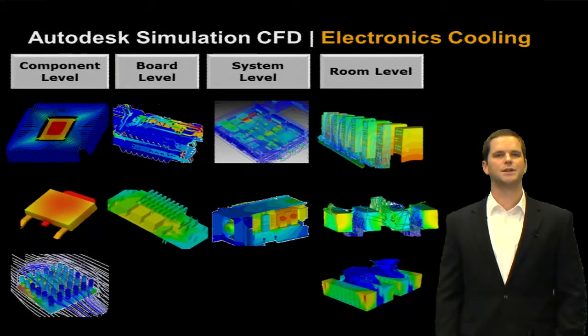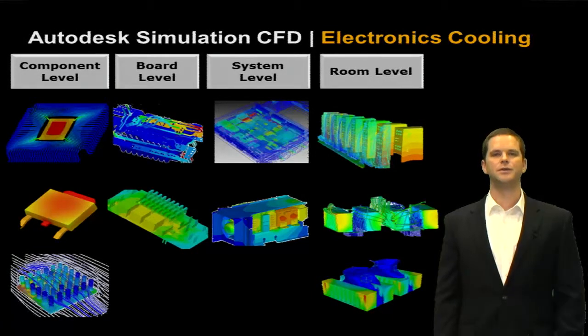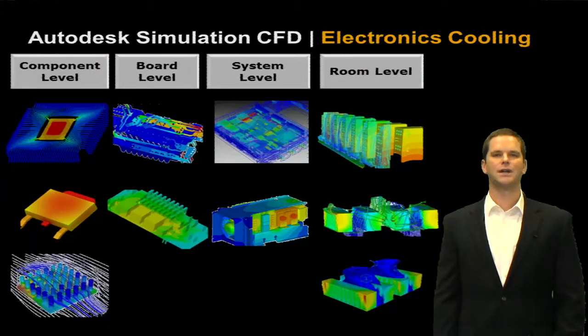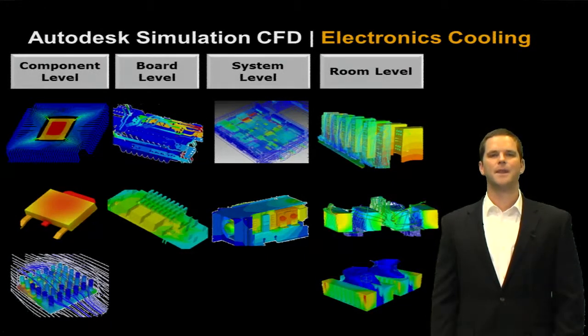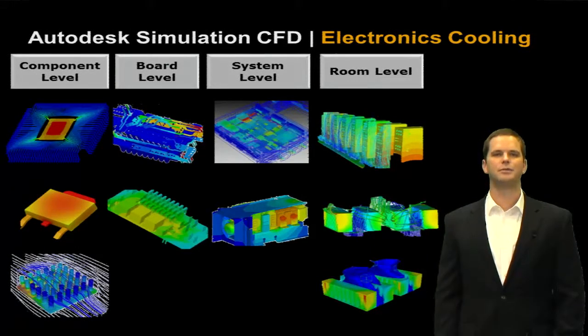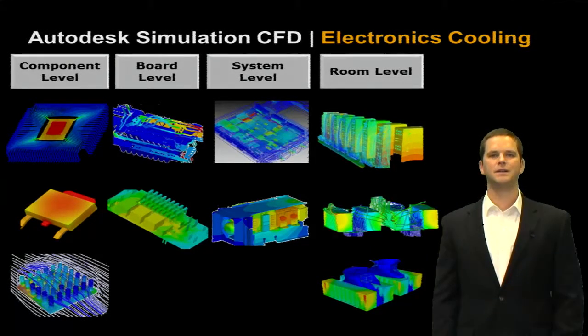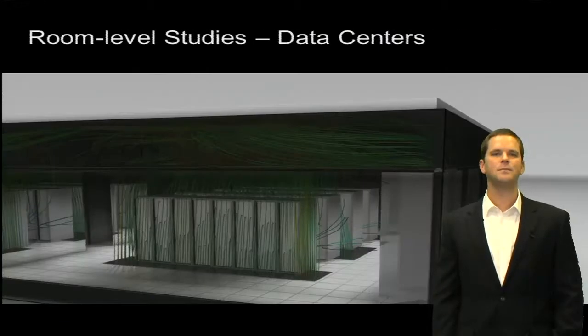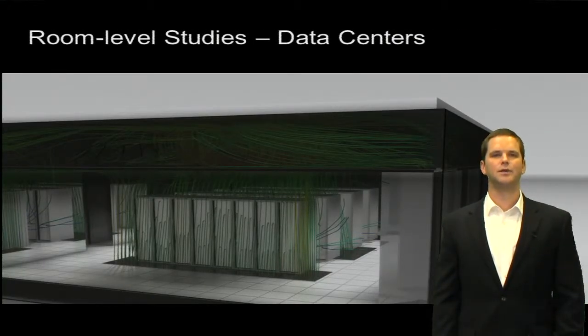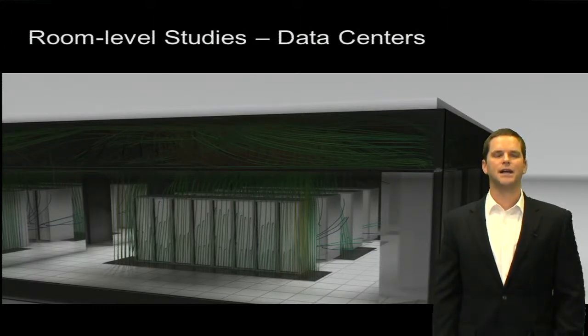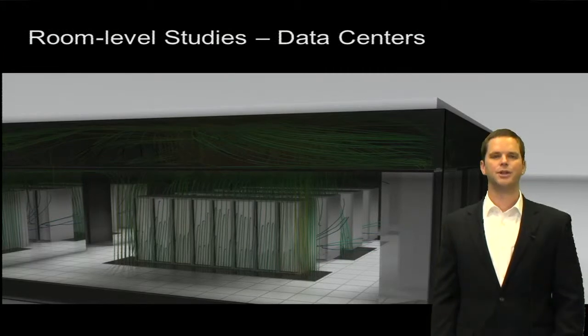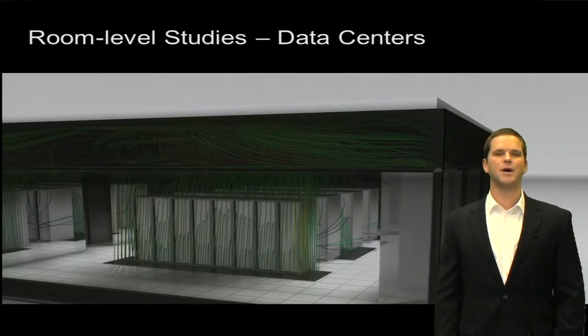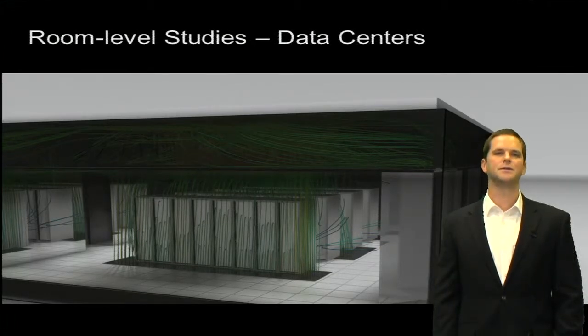And then we have a lot of firms doing room level studies as well. So some electronics companies will also run these more data center level studies to understand at a macro level what's happening to the racks, how are the air conditioners improving the cooling within the room and how does the air respond to both the buoyant effects and the forced nature in the sub floor. Here's a quick shot of a data center. So again, we have a lot of customers doing these types of studies where they're looking at that forced flow through the sub floor up through the racks and ceiling plenum and back, and strategically locating racks and tiles in order to maximize the cooling efficiency or power usage efficiency of their data centers.